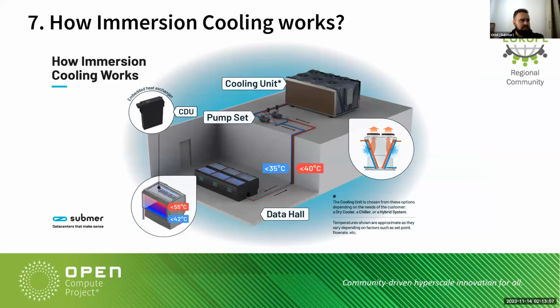So how does this work? This is just an explanation image, but we will have in a data hall the immersion tanks, with the connection of cold water and hot water. For example, cold water enters at 35 Celsius to have the tank at the 55 set point, which is the highest one. Then we have the hot water returning at 40, which in the dry cooler up here, we will bring back down to 35 again. So with a very efficient dry cooler and our very efficient Submer smart pumps, we can have this efficient environment where the heat is continuously being removed and exchanged.